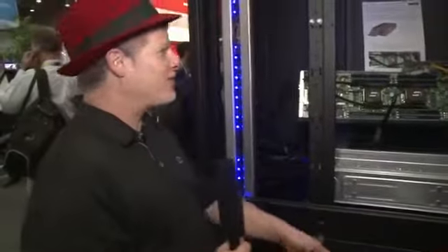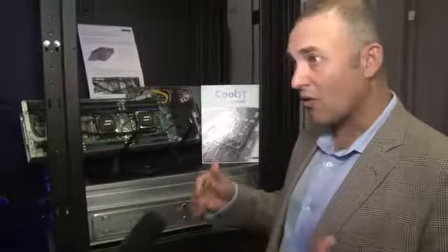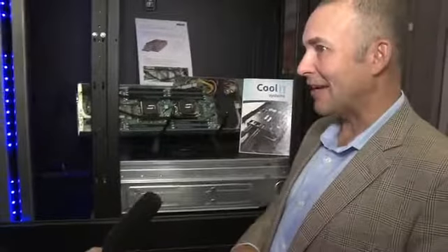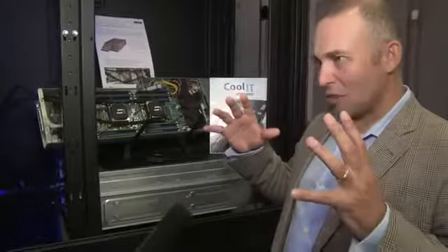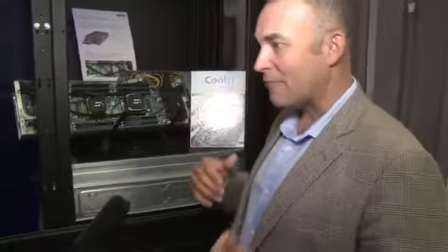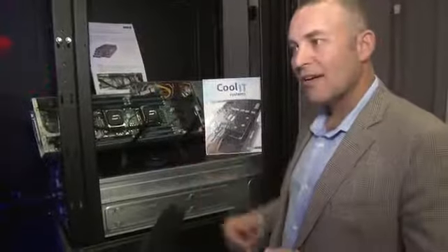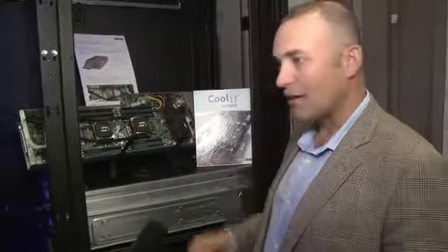This is all fine for someone building a new data center, but what about retrofitting? There are a lot of servers out there experiencing trouble with heat and power and cooling. We found it's actually quite a common scenario — people have a dedicated data center or cluster in a relatively small room, limited in air conditioning, but they want to increase their compute. We've got installations now taking place at several universities — Leeds, Binghamton, UNLV — where they were limited in air conditioning. We've retrofitted Dell servers, HP servers, SuperMicro platforms — it's relatively easy. We just take off the stock heat sinks, replace them with our modules, and as long as we can get the tubes in and out, we can liquid cool just about anything.